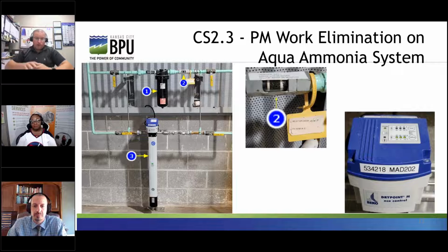Prior to the dryer, we had 51 total monthly work orders. Total labor hours for those was 88 hours. Total labor cost, $3,361. The last work order for the desiccant rejuvenation was on 10/21/19. Since then, that saved roughly 34 hours of labor in the last 2 years alone. Cost of the membrane filter was $1,500. ROI has already been achieved.